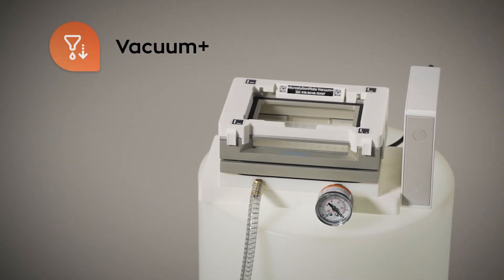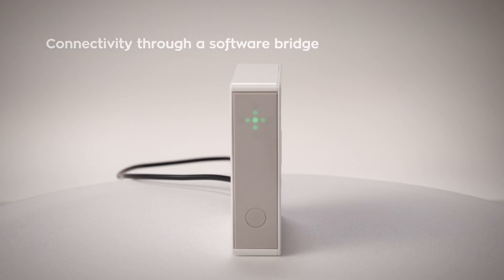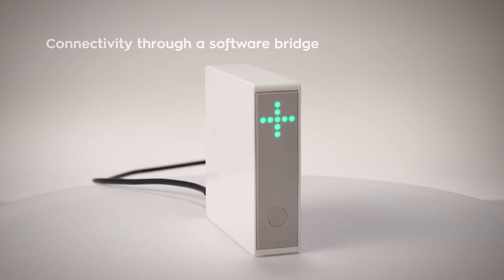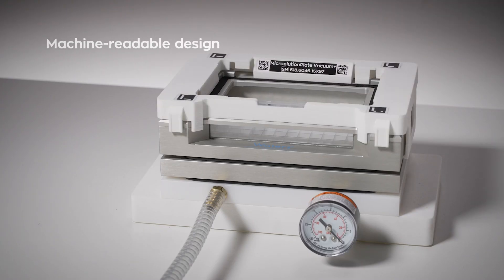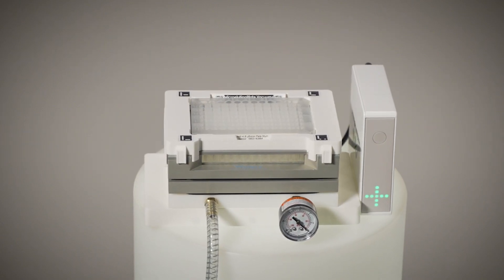Vacuum Plus is a hybrid device. We've designed it by bringing connectivity and semi-automation to an otherwise fully manual tool, the Waters Vacuum Manifold for Plates. This is achieved through two aspects. The first is by creating a software bridge between an otherwise non-connected pump and OneLab, so that OneLab can automatically turn any pump on and off to generate the desired vacuum. The second is by transforming the manual Vacuum Manifold itself into a machine-readable tool that can be easily integrated into an automation workbench with Andrew Plus, the pipetting robot. The core technology of this device remains the same though, creating negative pressure through a manifold to enable solid phase extractions.